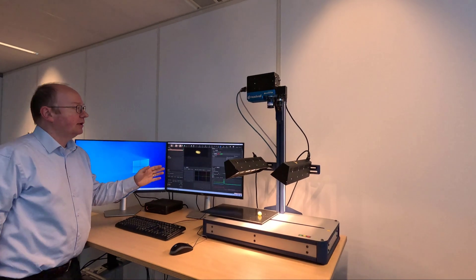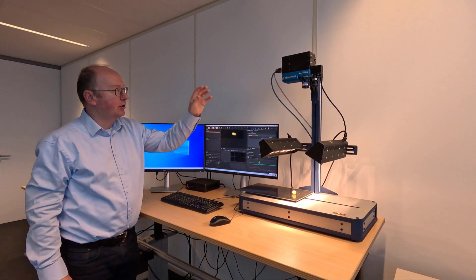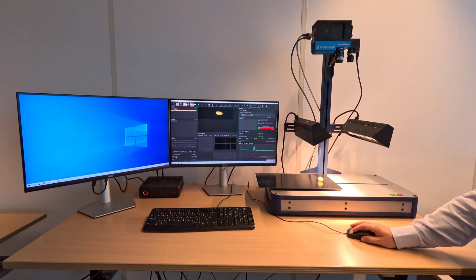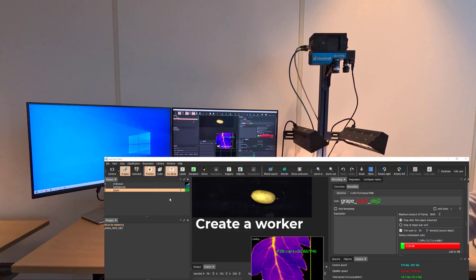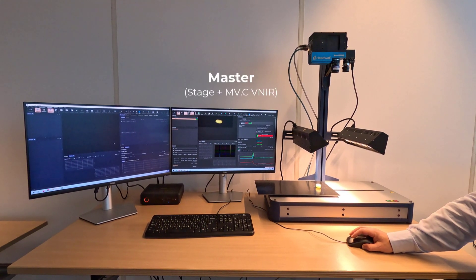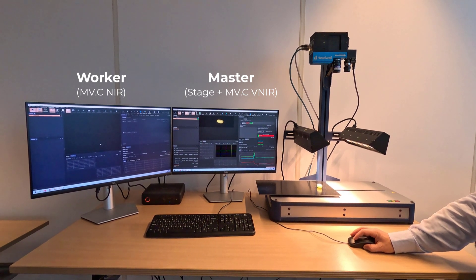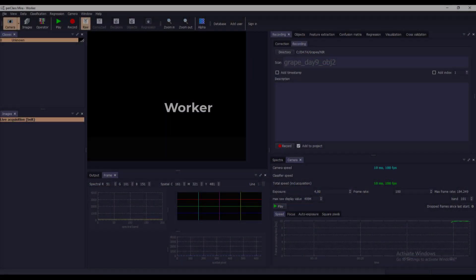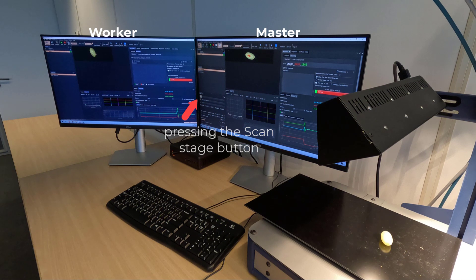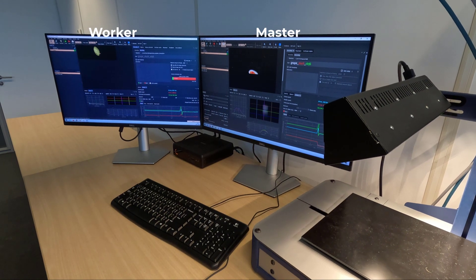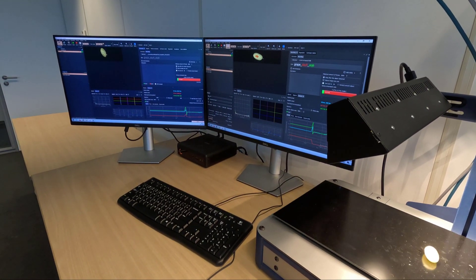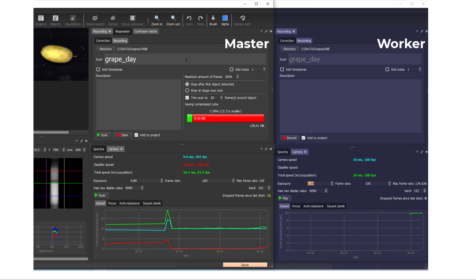Here we have a Headwall MVC NIR camera working from 900 to 1700 nanometers attached on PerClass stage, and next to it the tiny Headwall MVC VNIR camera working between 400 and 1000 nanometers. To work with dual scanning, you start by attaching PerClass Mira instance to the stage and one of the cameras as usual. We can fully set up the scanning with this camera as needed. To work with the second camera, we open a new instance of PerClass Mira from the camera menu. The original instance we call the master and the new one a worker. The worker connects to the second camera here to the MVC NIR system. As you can see, the worker window background is blue. This makes it easy to understand for any dialog box or a pop-up, whether you interact with the master or a worker. Using the dual mode is very simple. Each of the instances saves data to its own specific directory. When scanning, you only operate the master. When we click the scan button, the master notifies the worker and both instances start scanning. The filename is changed only in the master. Any change propagates to the worker.